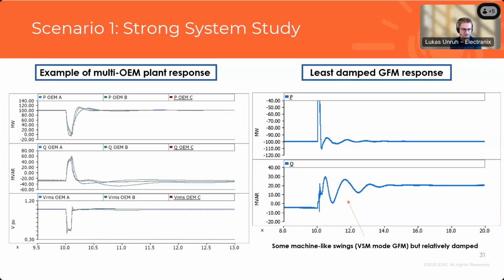On the left is an example of the multi-OEM plant response to a three-phase fault. You can see the three different grid forming OEMs here, their performances are slightly different, with some differences in the response at fault recovery, but generally there's no harmful interactions between them, and they're sharing proportionally before and after. So that was a good sign for us.